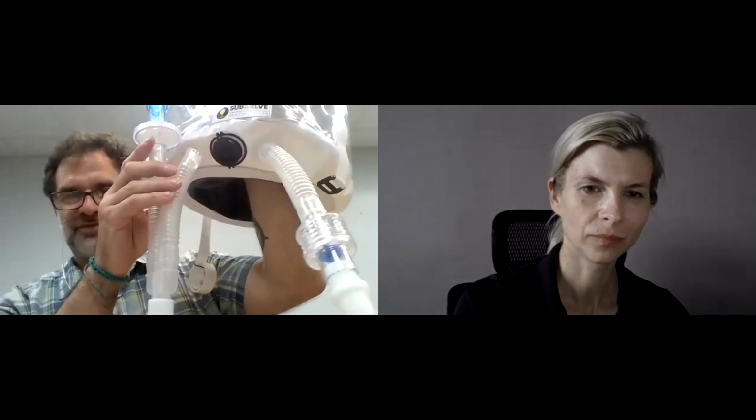Yeah. Nice. So the inspiratory side is that Respironics valve, which gives you potentially emergency breathing capability. And then your expiratory side is your backup drainage PEEP valve, and your primary filter and PEEP valve pointed up rather than down. Yeah. So definitely it's going to save the filter. It will last for longer.